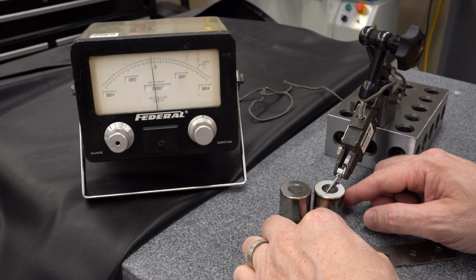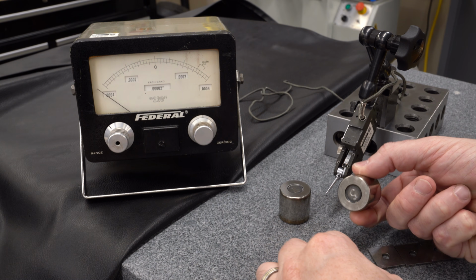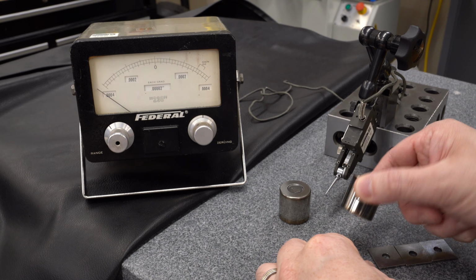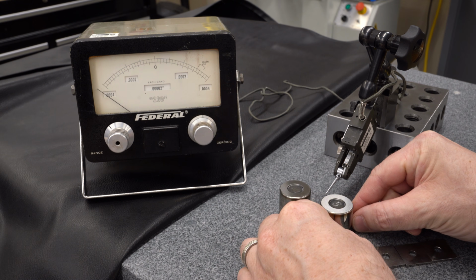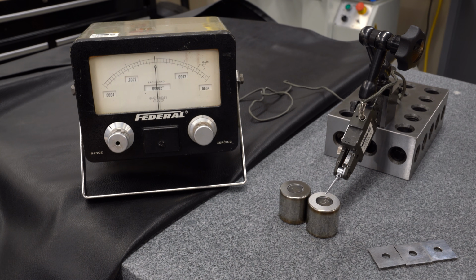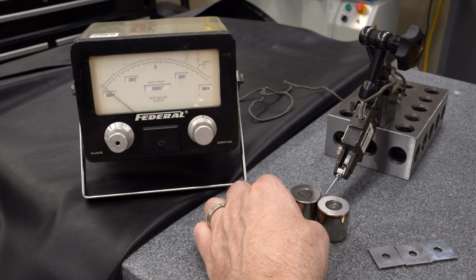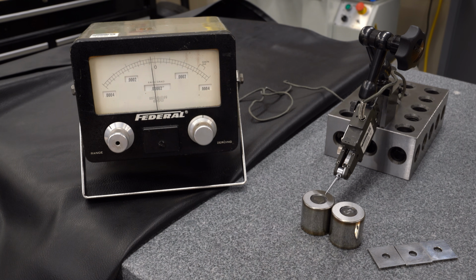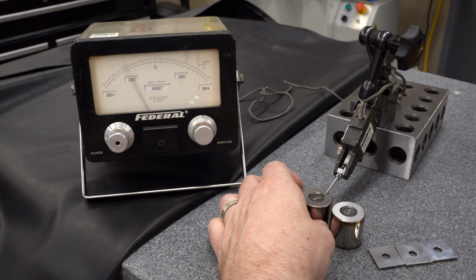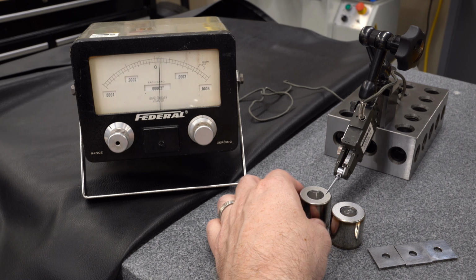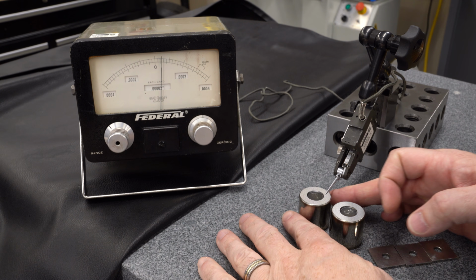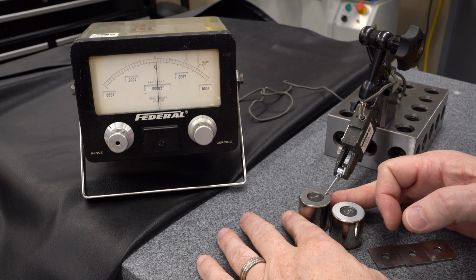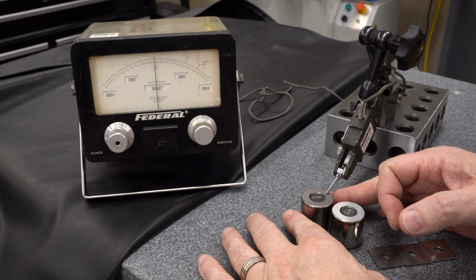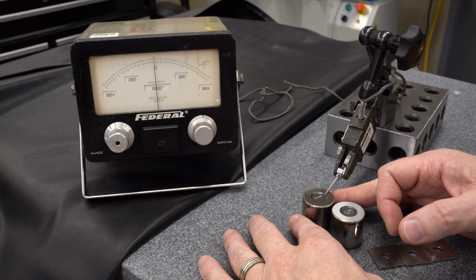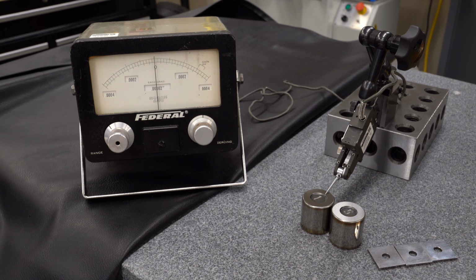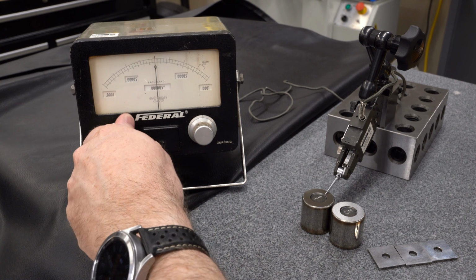If I fish around to different points on the top, we're moving around by 20, 40 millionths. The bottoms of these are definitely not flat. They were never ground. At least I never ground them. So the fact that these are as close as they are is actually a little bit surprising to me. But the tool seems to be working. I probably shouldn't be handling these too much because as we get into the really, really high resolution readings here, the temperature of the material is going to matter.